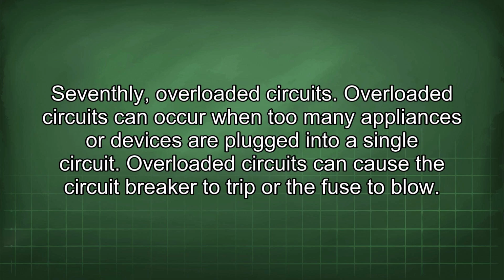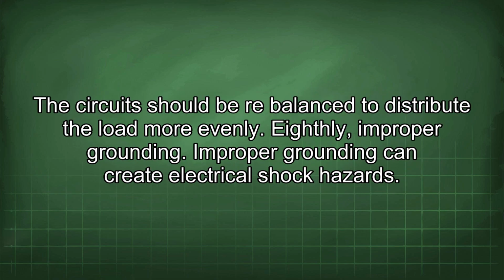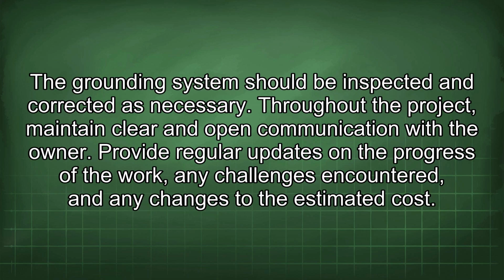Seventhly, overloaded circuits. Overloaded circuits can occur when too many appliances or devices are plugged into a single circuit. Overloaded circuits can cause the circuit breaker to trip or the fuse to blow. The circuit should be rebalanced to distribute the load more evenly. Eighthly, improper grounding. Improper grounding can create electrical shock hazards. The grounding system should be inspected and corrected as necessary.